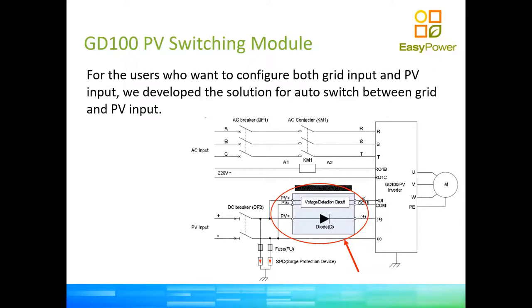A common question is whether switching between AC and PV can damage the motor or pump. The answer is no, because the switching is so quick and the motor has no stored energy to cause problems. The pump inverter controls the output current, so when the pump wants to restart it cannot draw excessive current — the inverter limits it. You will never damage the pump because of switching with the pump inverter, whereas running directly from the grid without a constant-current start can damage it.